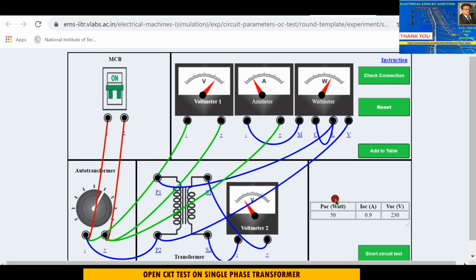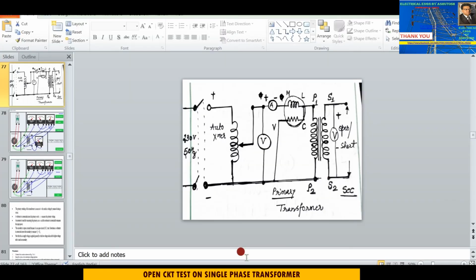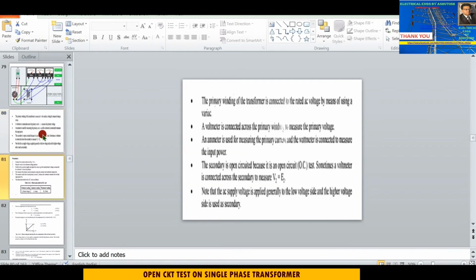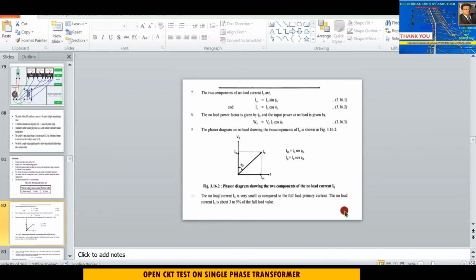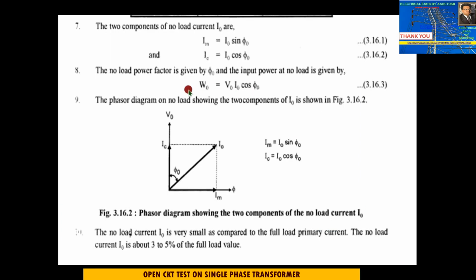So you can note down all the readings, and we can find out the different parameters by using open circuit formulas. You can see here these are the readings, and these are the open circuit parameters. This is the magnetizing current, Im or I phi equal to I0 sin phi 0. This is the core loss component, IC equal to I0 cos phi 0, and this is the no load power factor. This is the no load power formula, W0. From this formula you can calculate the no load power factor. So W0, the iron loss, is equal to V0 I0 cos phi 0.